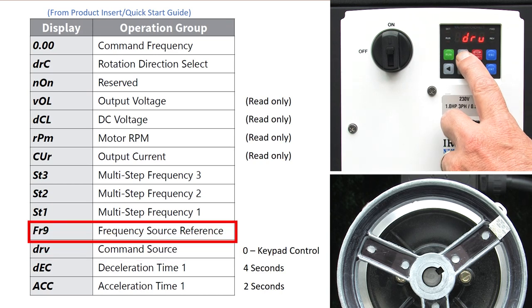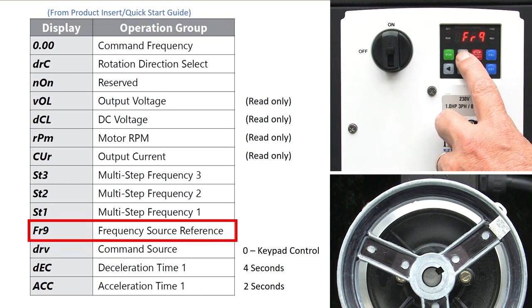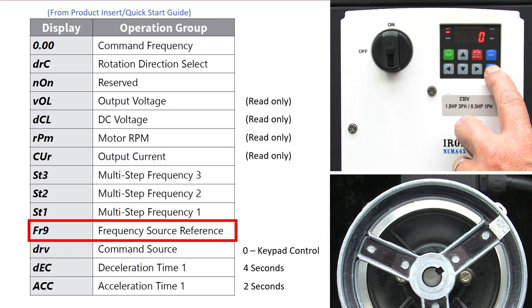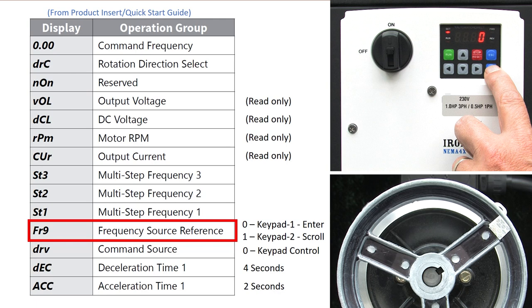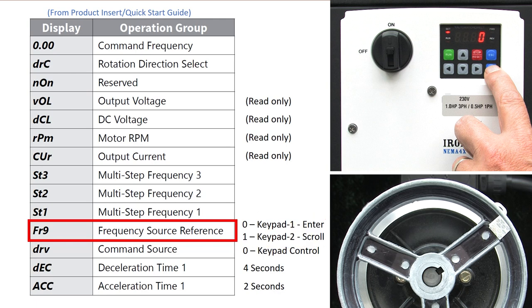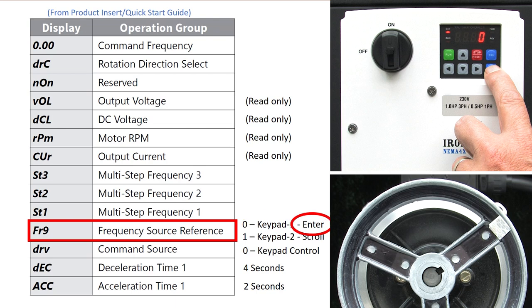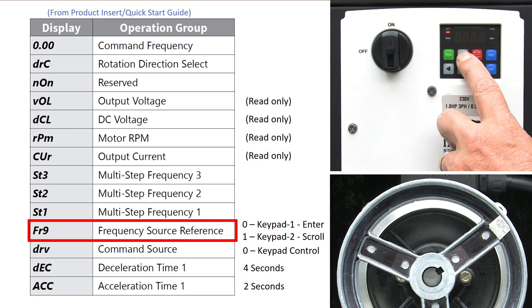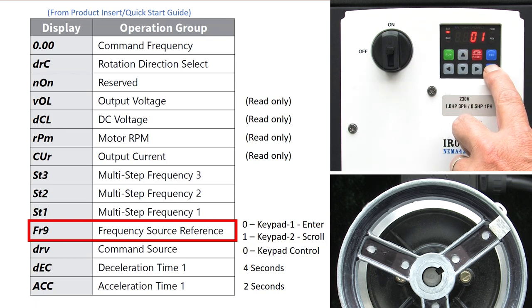If I up arrow one more time we see the frequency source parameter. Enter into that. There are two ways to control the frequency from the keypad. The manual refers to them as keypad 1 and keypad 2. Keypad 1 says don't change the frequency until you hit enter to select it and enter again to accept it. Keypad 2, which is a 1, says change the frequency as you scroll. Let's select that one and hit enter to accept it.